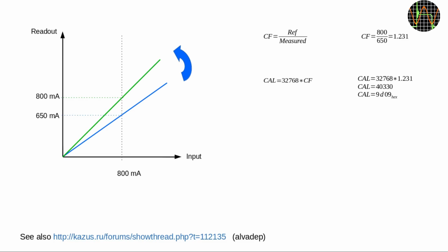It's surprisingly simple if you consider this example. A true value of 800 milliamps is applied, but instead of 800, the UT210E reads only 650. First, we calculate a correction factor, CF, which is the reference divided by the measured value. So 800 divided by 650, which is about 1.231. To store this floating point in the EEPROM, it is simply multiplied by 32,768, and all digits after the decimal point are dropped. In the example, we would have a value of 40,330 or hex 9D09, and that value is what you would find in the EEPROM.